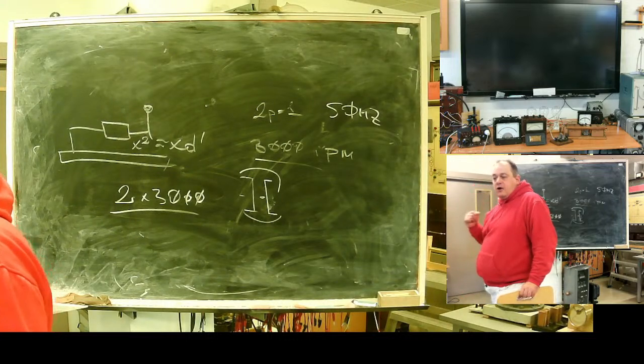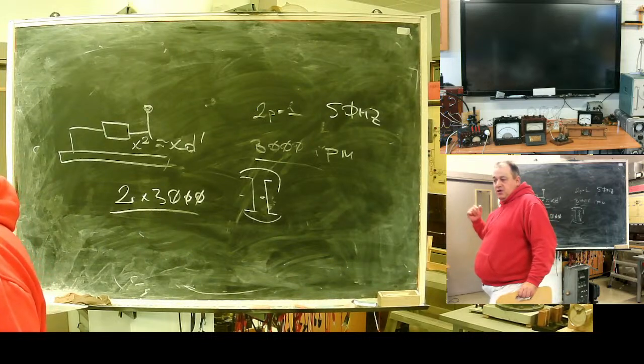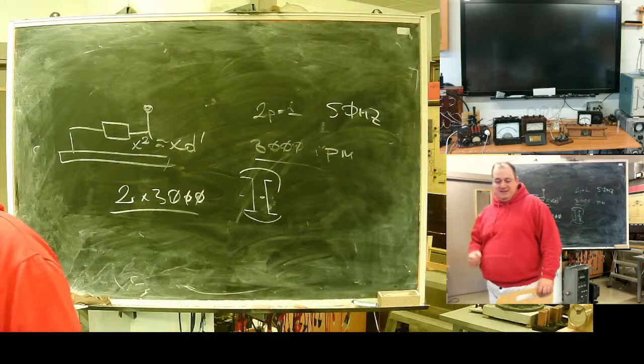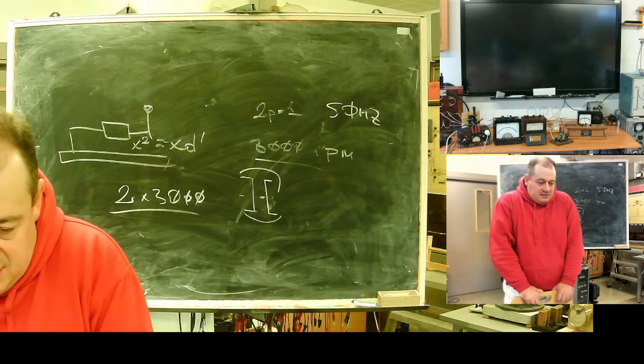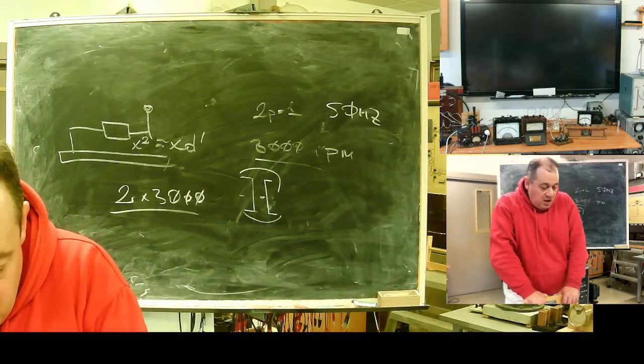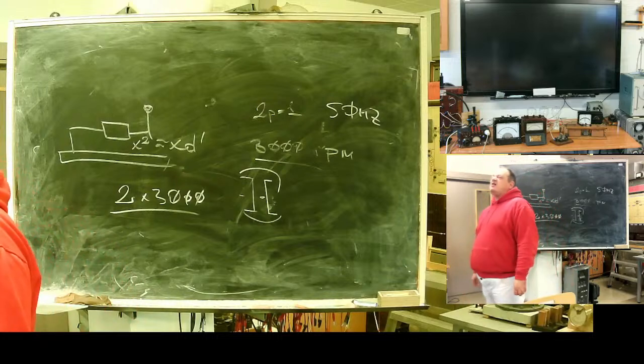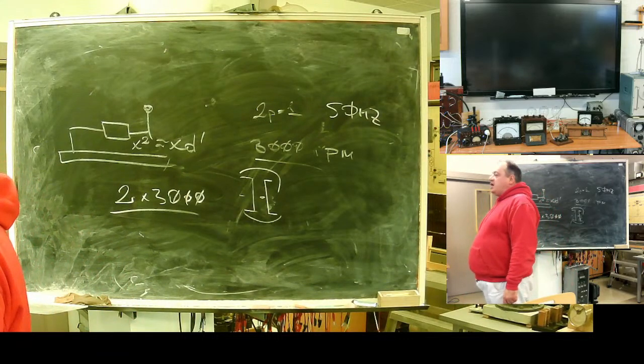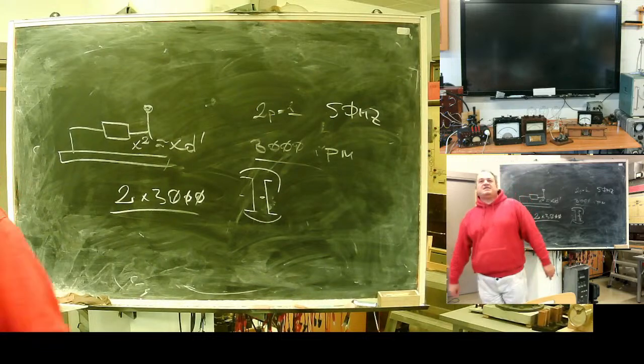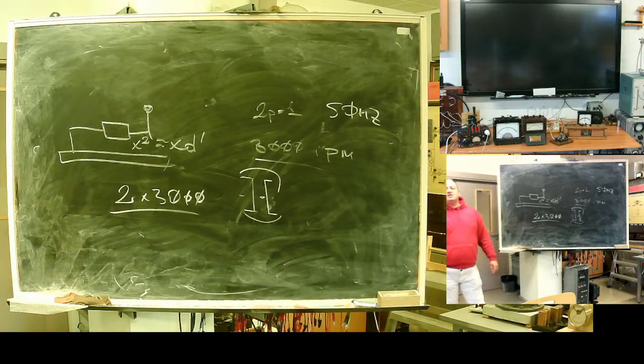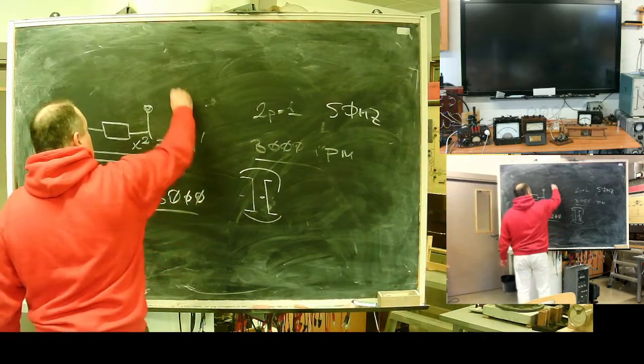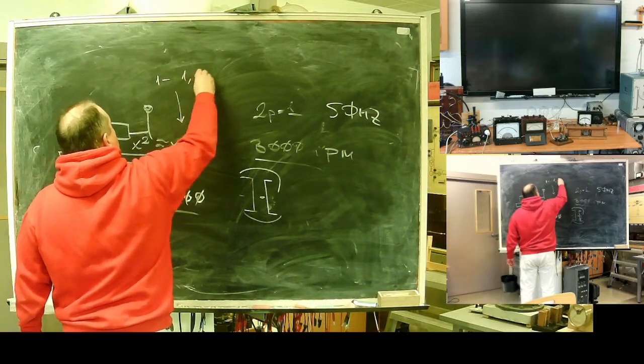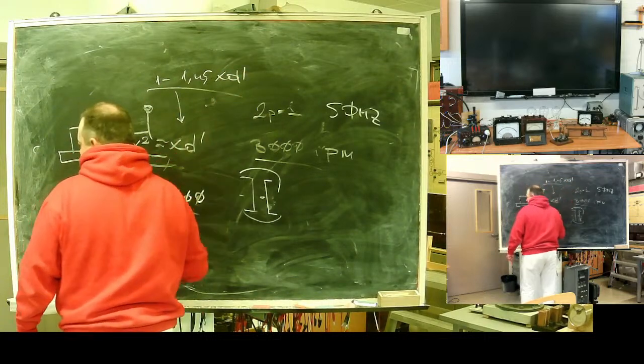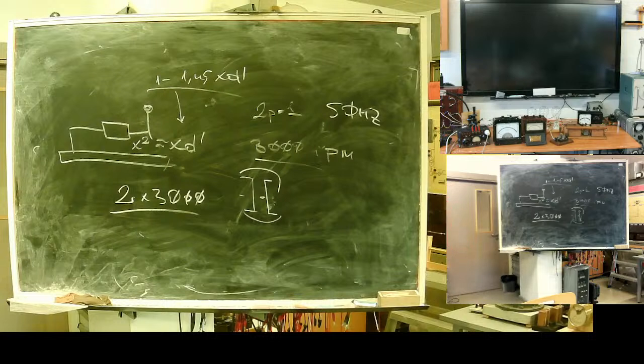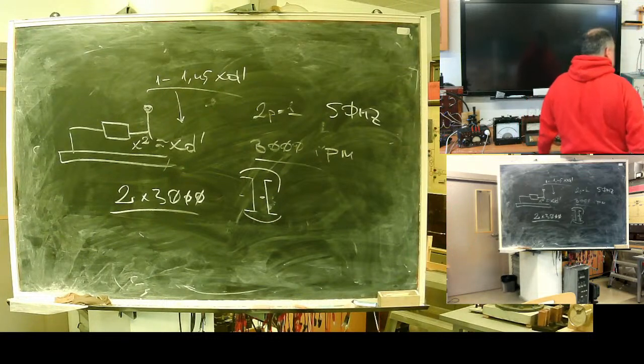Cases are known when, without any overcurrent, just because of non-symmetry, in this book you can find an example. In Germany, a 400 megawatt generator was completely ruined by negative sequence. So for this machine it's a danger, but the reactance is higher because the current has no good path to close. Actually, here it can be from 1 to 1.5. It's a difference. Usually manufacturers do supply these digits.